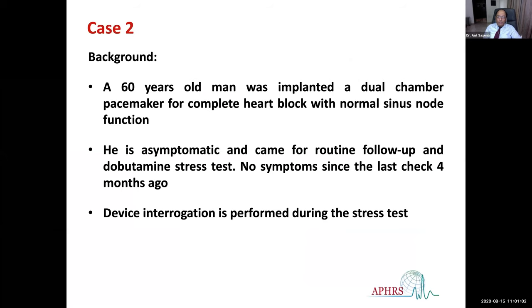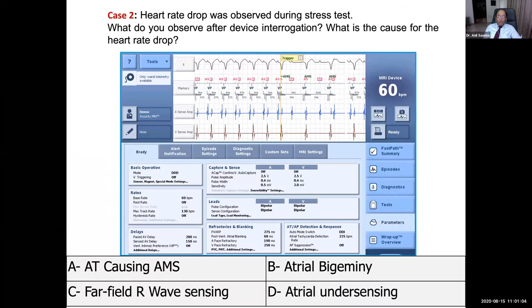Device interrogation is performed during the stress test, because in dobutamine stress testing we sometimes have to increase the pacing rate by the device, using the programmer itself. This is what we find during the dobutamine stress test: as the heart rate increases beyond a point, it suddenly drops. So what are we dealing with?